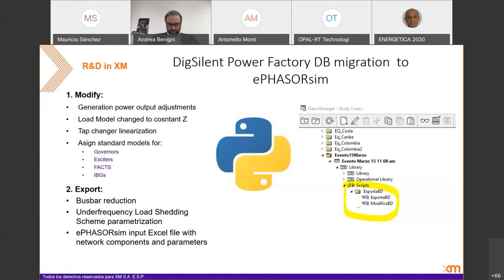Basically, we're running in two steps. The first step is the modification of some parameter changes in the original DigSilent database. The first thing we do is adjust the generation power output of some generators to make it fulfill their limits. The second thing we do is change the load model to constant impedance. The third thing is the tap changer linearization, which in our DigSilent database is not modeled in a linear way. Finally, we assign some standard models for governor, exciters, FACTS devices, and inverter-based generators.